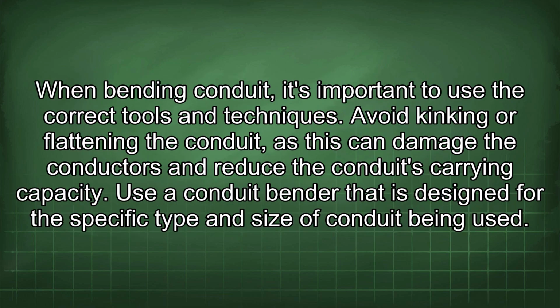When bending conduit, it's important to use the correct tools and techniques. Avoid kinking or flattening the conduit, as this can damage the conductors and reduce the conduit's carrying capacity. Use a conduit bender that is designed for the specific type and size of conduit being used.